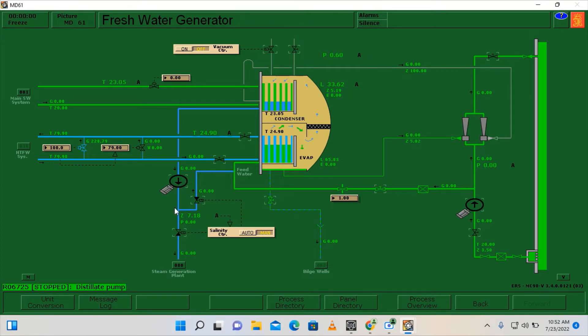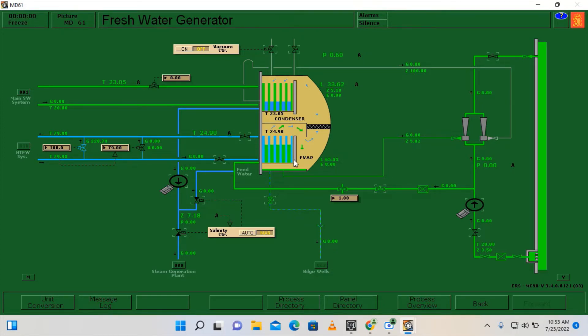On the condenser section, this is where the distillate will be formed and it will be suctioned by our distillate pump. If we have a high salinity then it will be dumped going to our sea water, and if we have a low salinity within normal range then it will be going to our fresh water tank. This is our HT water which is going to our fresh water generator and this will boil the sea water which is being fed by our ejector pump. This is the sea water which is coming from our main sea water system, which will be fed going to our condenser section to cool down the vapor.